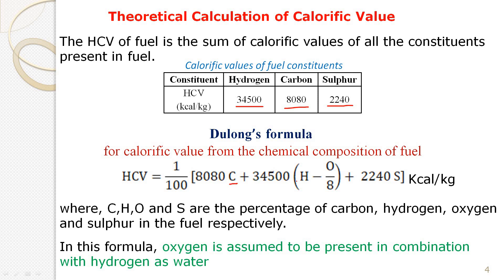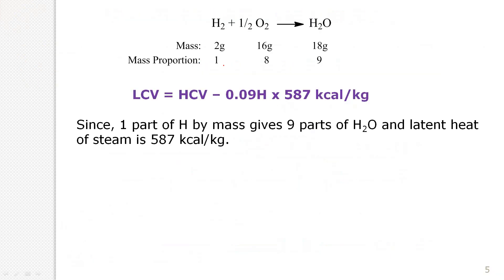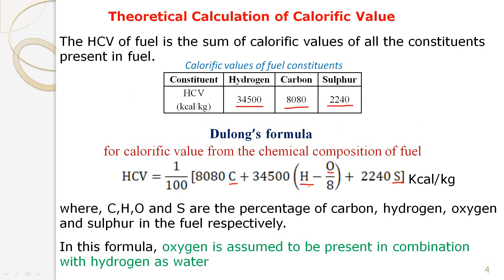Here, C, H, O, and S indicate the percentages of carbon, hydrogen, oxygen, and sulfur present in the fuel. We subtract the hydrogen percentage as (H − O/8) because one part of hydrogen combines with 8 parts of oxygen. If oxygen is present in the fuel, it is combined with hydrogen in the form of water, so that hydrogen is not available for combustion and we must subtract that value.